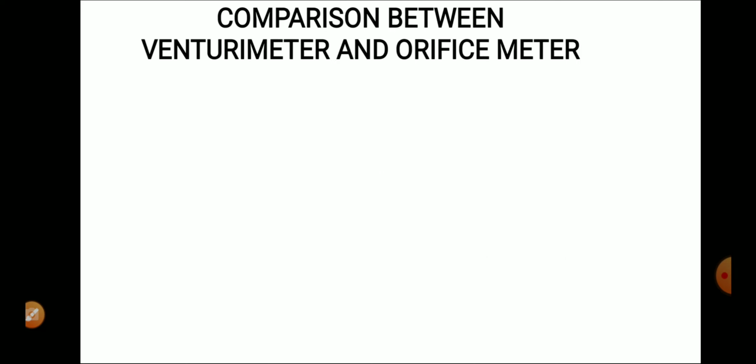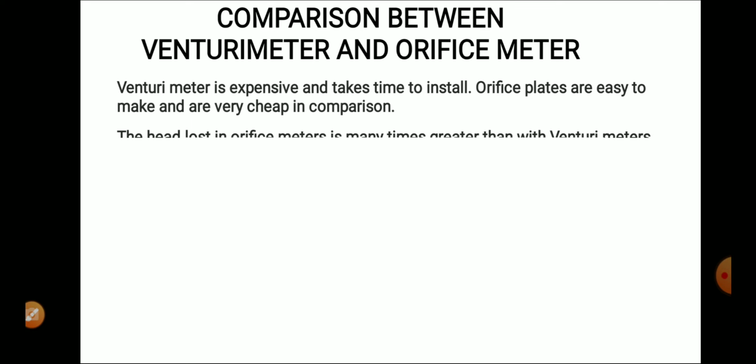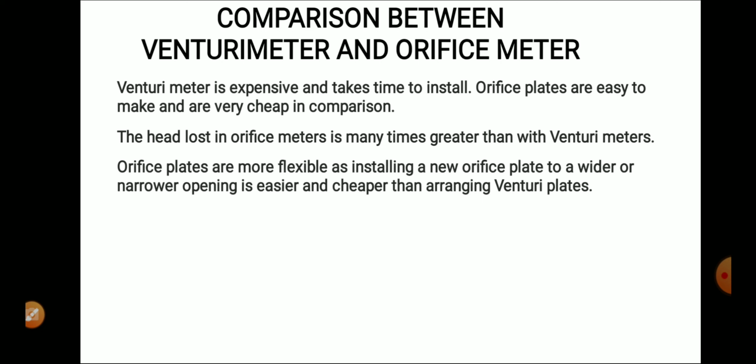Comparison between Venturi meter and orifice meter. Venturi meter is expensive and takes time to install, but orifice plates are easy to make and are very cheap in comparison. The head loss in orifice meter is many times greater than with Venturi meters. Orifice plates are more flexible, as installing a new orifice plate to a wider or narrower opening is easier and cheaper than arranging Venturi plates.